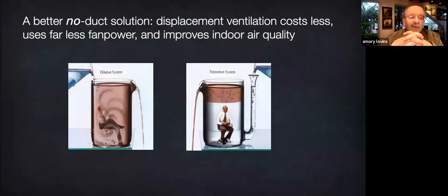Even more basic than fan efficiency is the strategy of how we distribute fresh air in a building. The standard method is to blow fresh, cool air, or maybe not so fresh, down from the ceiling. That's called turbulent induction, and it mixes the relatively clean supply air with the dirtier air that's already in the room. And therefore, any fumes, germs, CO2, and so on all get mixed into the air you breathe, as shown on the left. That is unhealthful, noisy, inefficient.